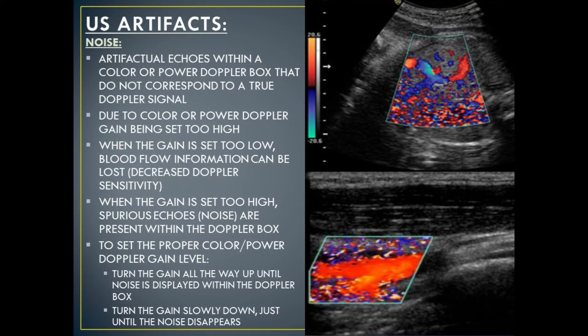Noise is the next type of ultrasound Doppler artifact. Noise is artifactual echoes within a color or power Doppler box that do not correspond to a true Doppler signal. This can be due to the color or power Doppler gain control being set too high. When the gain is set too low, blood flow information can be lost, which is decreased Doppler sensitivity. When the gain control is set too high, spurious echoes, or noise, are present within the Doppler box. To set the proper color or power Doppler gain level, turn the gain all the way up until the noise is displayed within the Doppler box, then turn the gain slowly down just until the noise disappears.